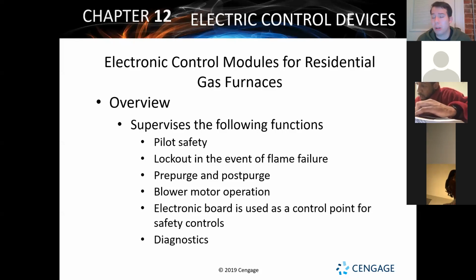It's going to make sure to ignite pilots correctly, if it's got an automatic pilot, an intermittent pilot, or a standing pilot. Again, things you're going to learn more about. And so all these different things is what it's going to look at to make sure that that gas furnace is burning, operating, and heating properly. That's the big thing. And then with the modern ones, again, it's going to modulate and control. The modern gas furnaces go beyond just controlling the speed of your fan motors, because that's all that's running on those. But it's also going to control the speed of a gas valve and how much gas is coming through to be burned and everything like that. So these are getting really, really cool.